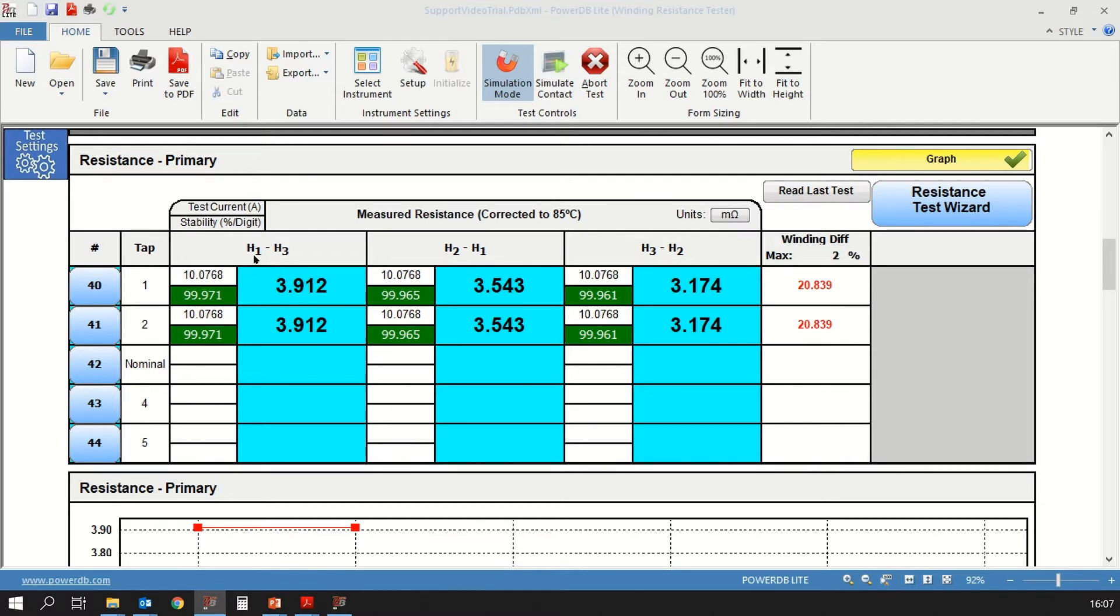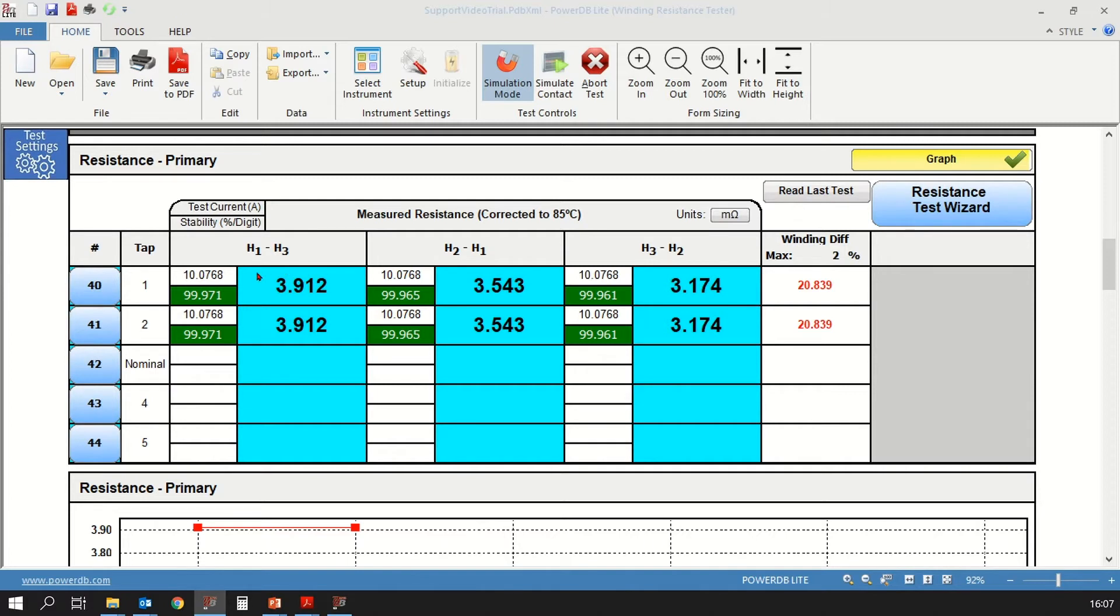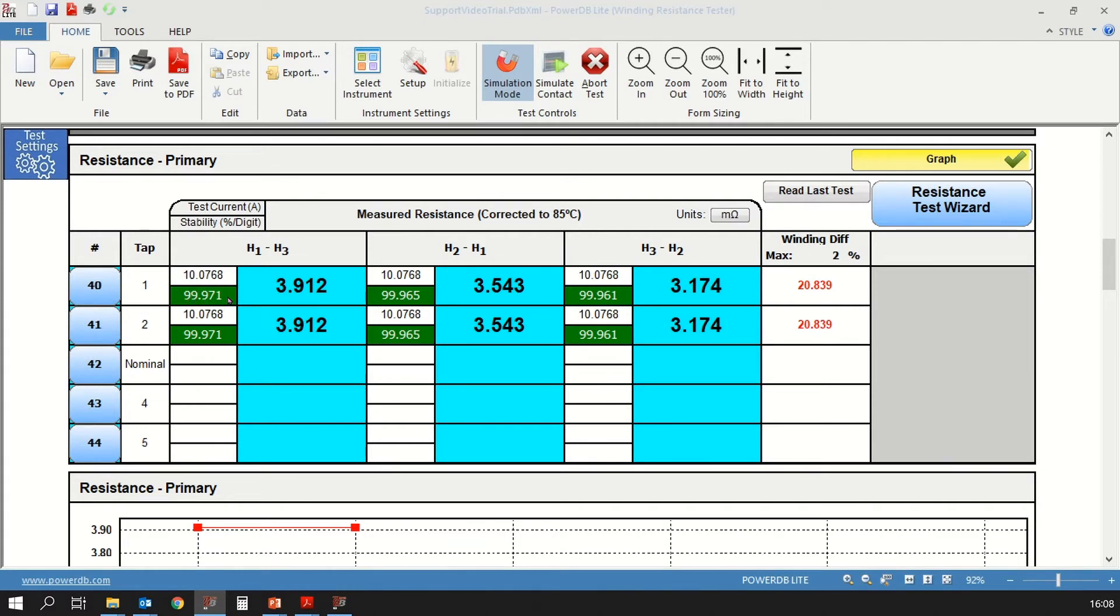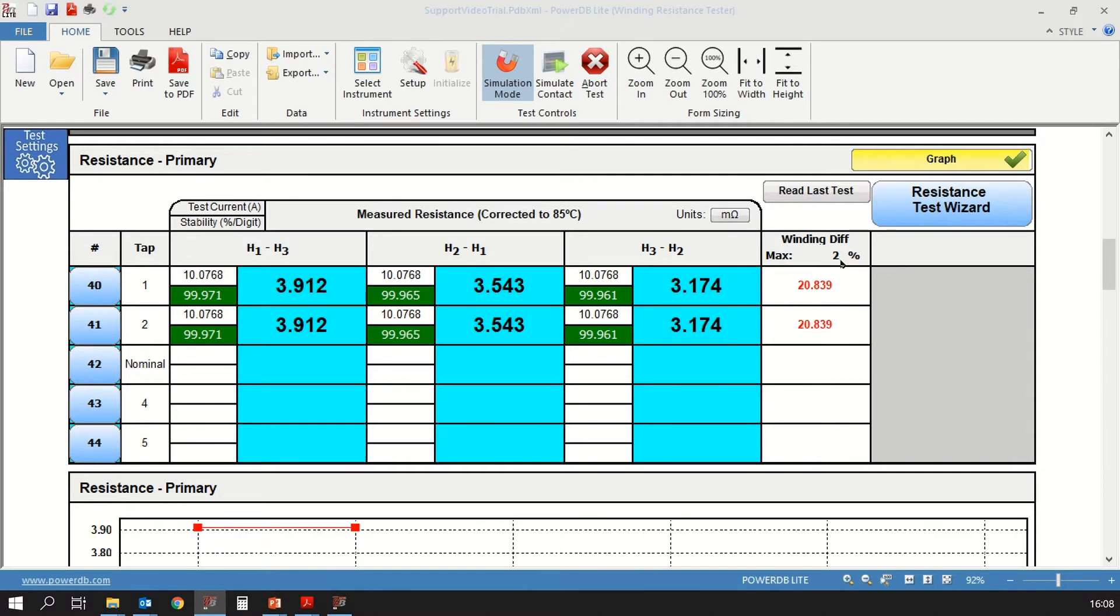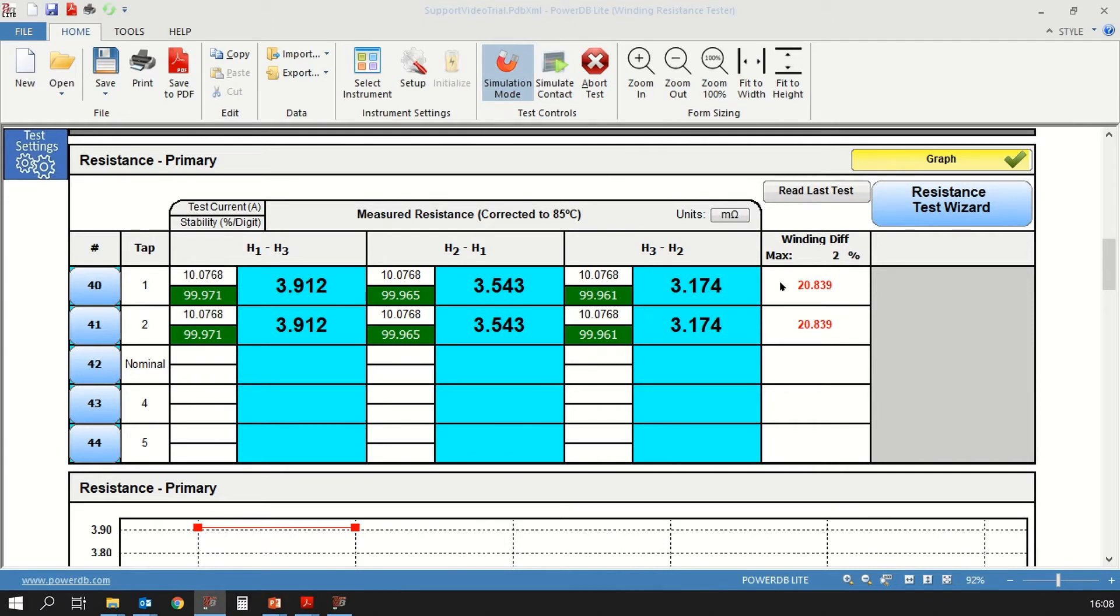Next, you have H1 through H3 that would be A phase, H2 to H1 that would be B phase and so on. For each tap and each reading, you have three values. The first biggest value that you can see is the resistance value. Then on the top left, you see a 10.07 value. That is the test current that was used. Below that, the values in green background are the stability reading for that resistance measurement. You have the same for each phase. To the right side, you have the percentage between the phases for winding resistance. You can see that the maximum can be 2%. Now because we are using the simulation mode up here in PowerDB, these values are not real values corresponding to an actual transformer, so we have a higher than 2% winding difference, but I wouldn't regard that very important.